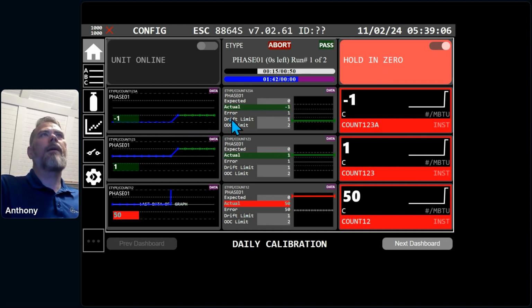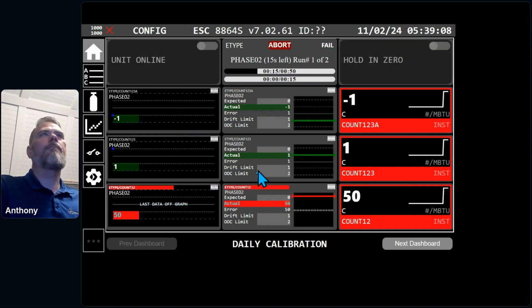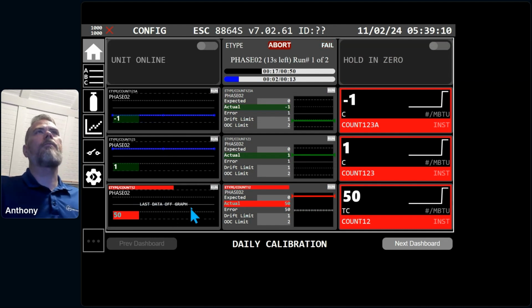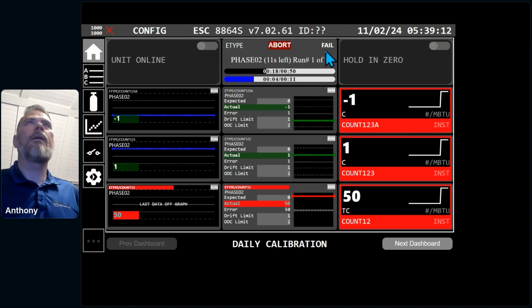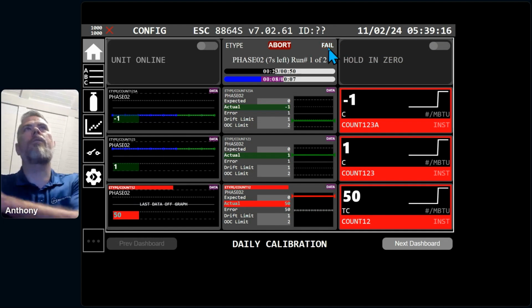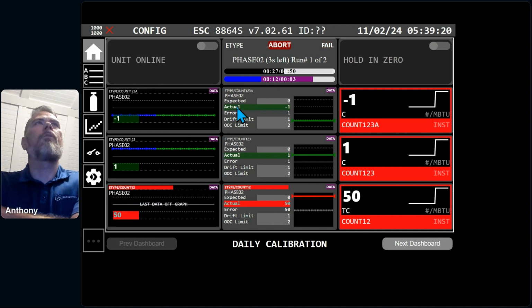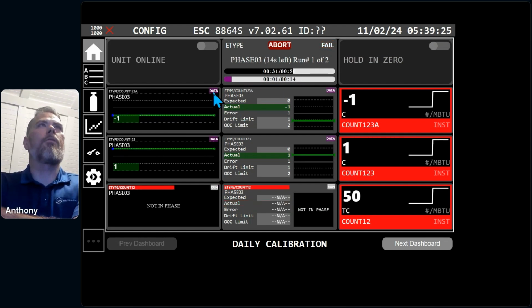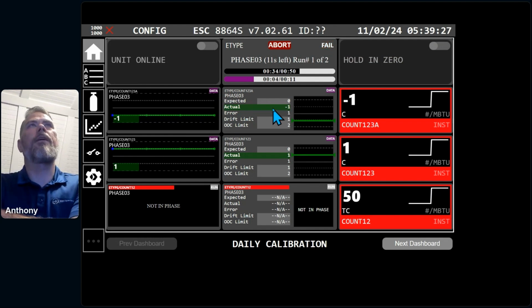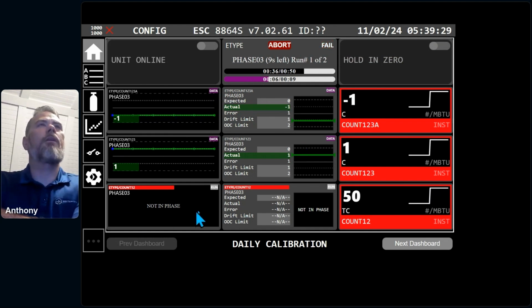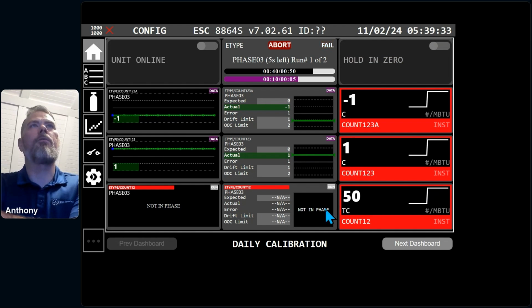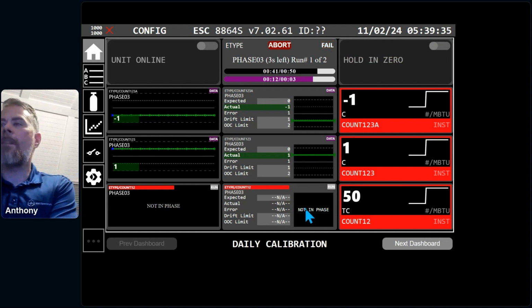And so now that I'm fully in passing and not even drift, I'm going to release it. Of course, this one's going to fail because it was outside of it, and we'll see that status and see it failed. And so now our calibration is flashing fail. If we get a fail or a drift, we will flash that status for the calibration. You can see as we continue on that we're showing data for this one. The last phase is data. So there's our run, then our data for the entire phase. And if a channel is not in a phase, we will display that here on the graph, not in phase, to give you an indication that it's not in phase.